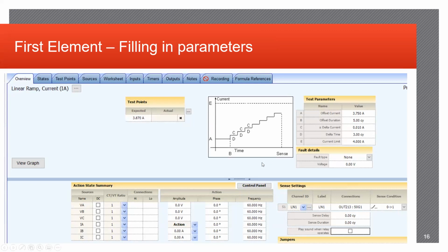So as shown here, you can see that the test engineer filled in all the parameters that would be necessary. It's got the 3.87 amps for the expected test point. Got your offset currents, offset durations, and your current limit, which would usually just be a little bit above your expected value, as the relay should be expected to detect values down to the lowest decimal you can imagine. As well as a sense connection. Again, we're utilizing this out 213, which was a spare contact, but we're actually manipulating it to be a 50G1 pickup contact. So when that element picks up during your test, output closes, the test set detects it and stops the test.